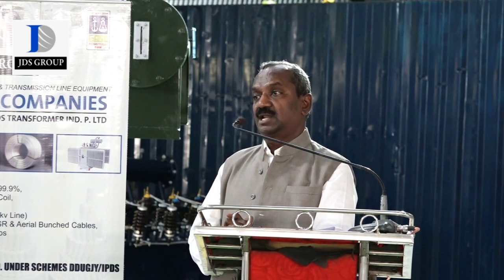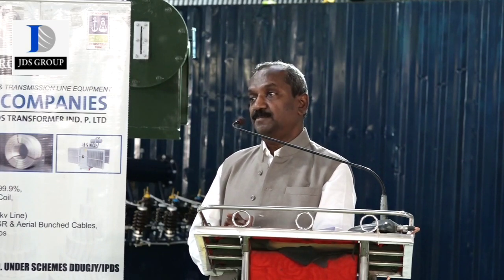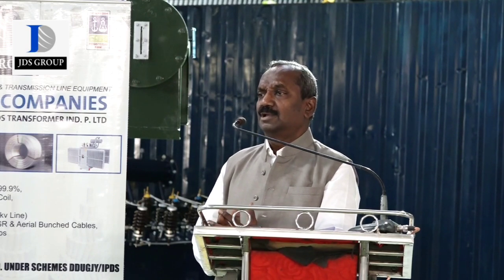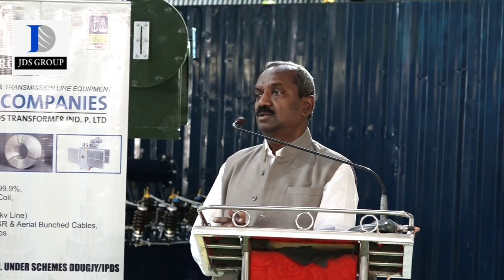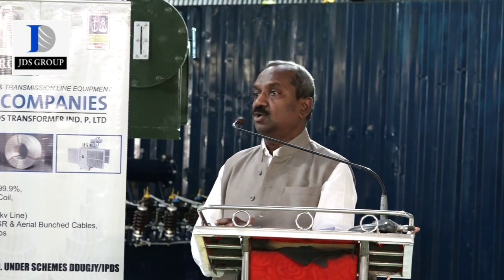Maintain breather regularly, arrest leakages at the earliest opportunity, test your transformer oil periodically, at least at the most also once in a year, monitor the values, and if required take the corrective action like filtration or replacement.